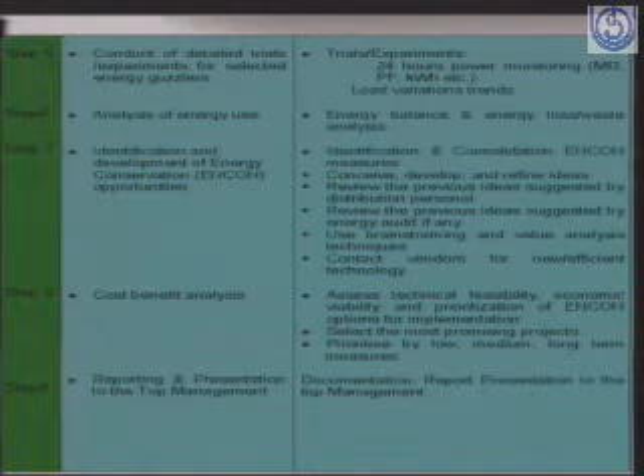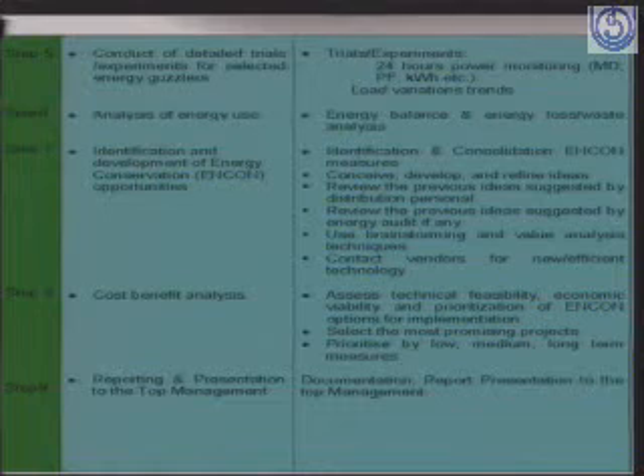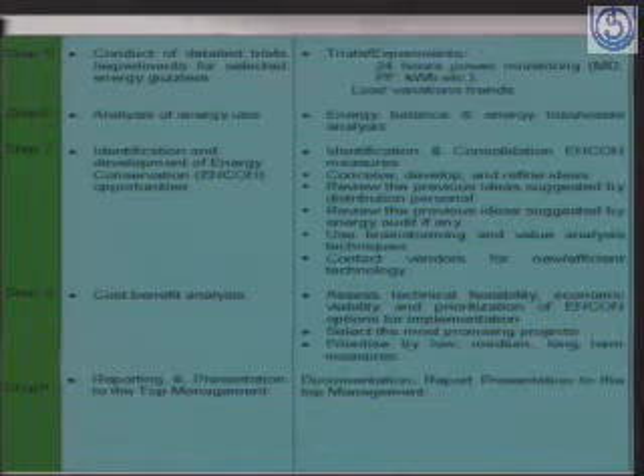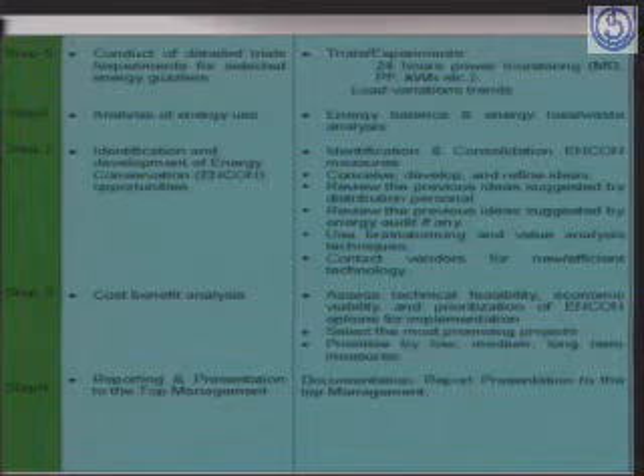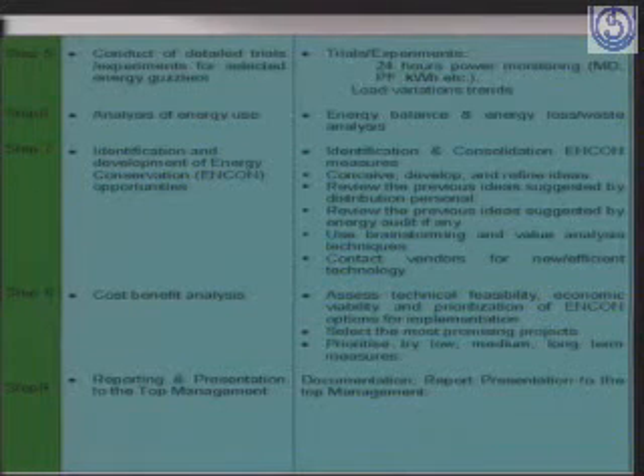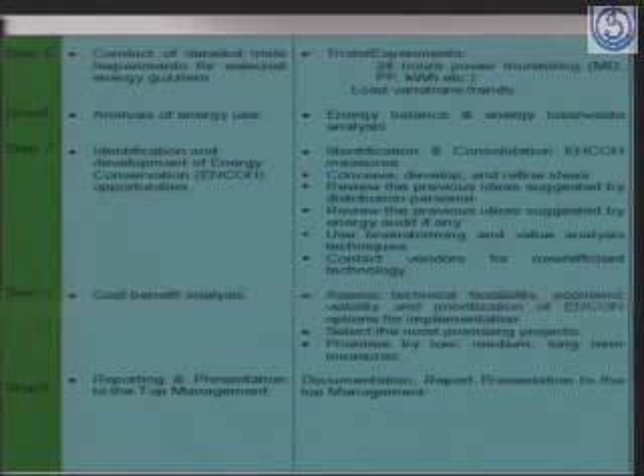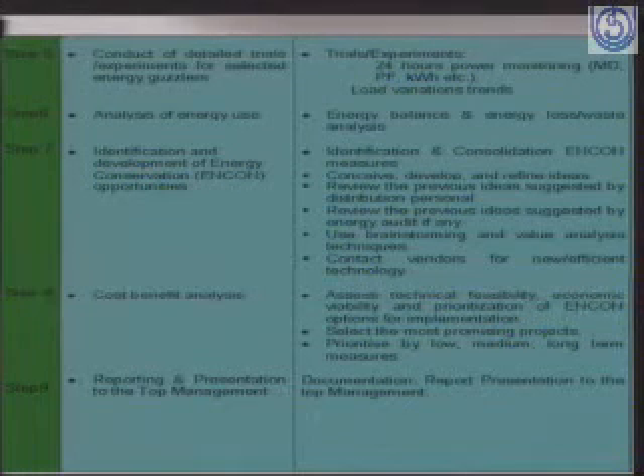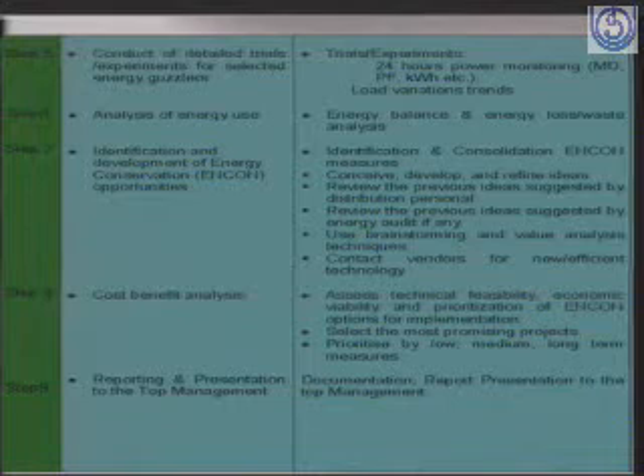Basically the trials are conducted which record maximum demand, power factor, kilowatt hours, etc., and then the load variation trend, because load is not constant, it keeps on varying with respect to time. Morning load is different, evening load is different, and afternoon load is different. So these trials are carried out to find out the load variations. Then analysis of energy use, step 6. Under this, the energy balance and energy loss and waste analysis is carried out. And under step 7, after such assessments have been made, energy conservation opportunities are identified.